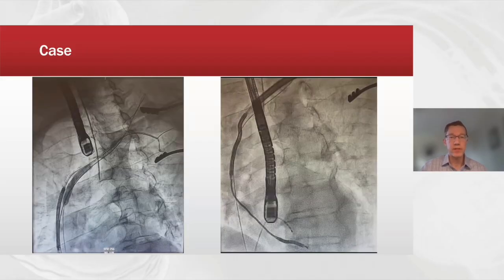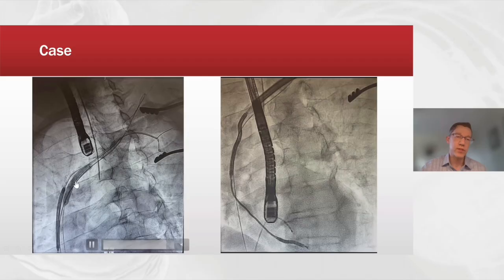So back to our case, we placed a number 2 lead locking stylet and dissected out the high voltage cables separately and tied those off. We performed lithotripsy from near the clavicle down towards that high burden of calcium area here, which you can see on fluoroscopy, and lining up the center of the balloon where that highest emitter is located.